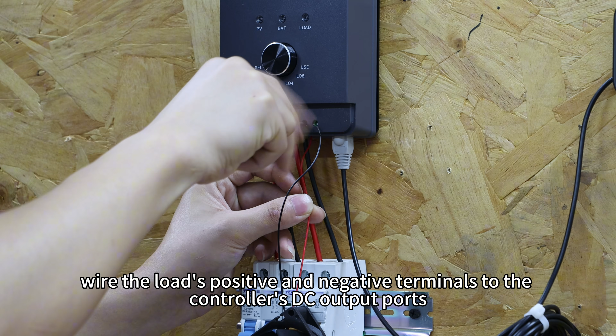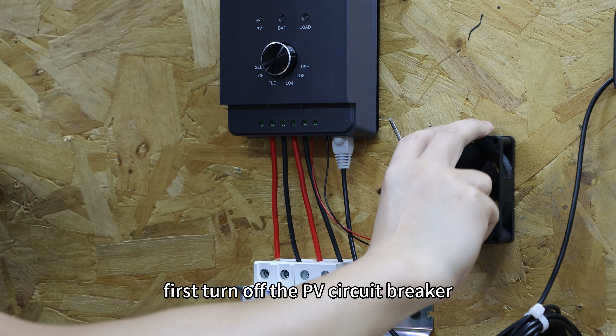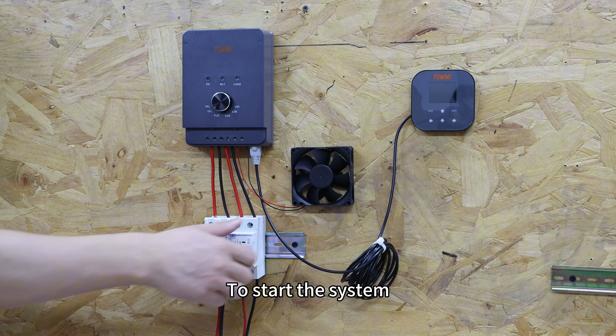Important, make sure the entire system is powered off before connecting the load. The shutdown sequence should always be: first turn off the PV circuit breaker, then turn off the battery circuit breaker. To start the system, first turn on the battery breaker to power up the controller, then close the PV breaker. The PV system will now run normally.